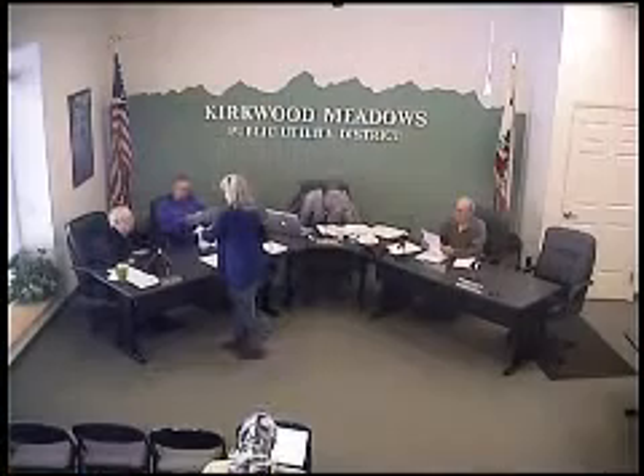Thanks, Michael. The reactor that we specified got bids for the KMPUD substation. It's basically a large inductor, but it's going to be installed in something that will look pretty much like a pad mount transformer, a green transformer. It's required due to our understanding and analysis of the underground cable system. This very long underground cable system will have a lot of capacitance, and this reactor is needed to offset that and maintain reliable voltages on our cable system and at the powerhouse.